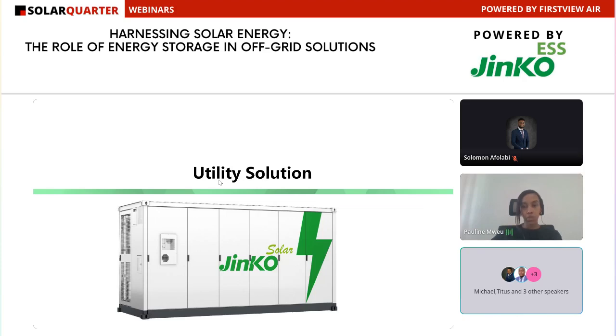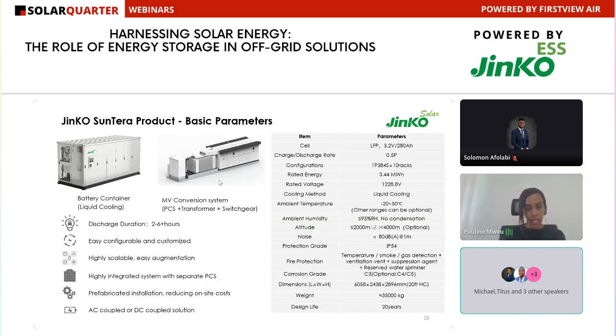We have the utility solution, or the SunTera, which is a standard solution rated 3.44 megawatt hours, and you can also parallel them up to 4 units. The cell technology is also lithium iron phosphate, and the battery container comes separately from the PCS transformer and switchgear - so they come as 2 separate containers. It supports both AC and DC coupled solutions.